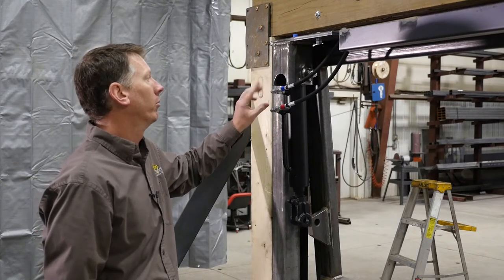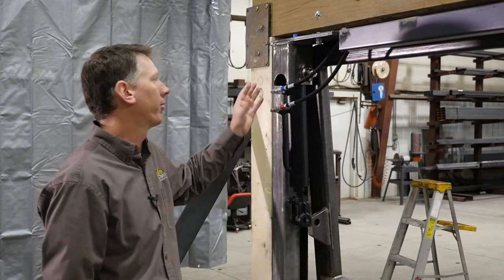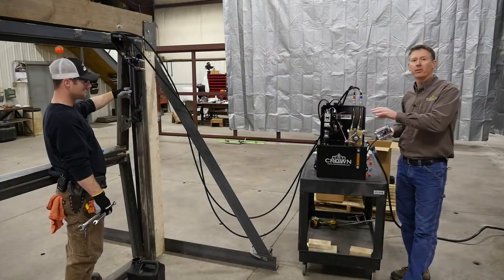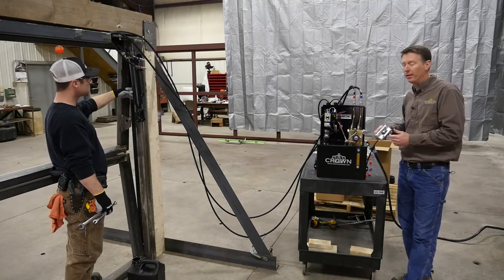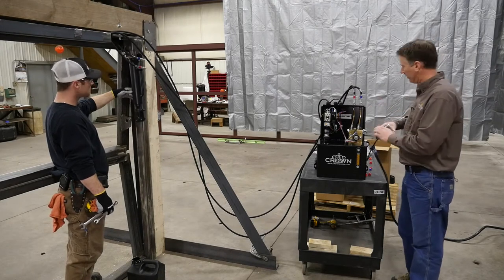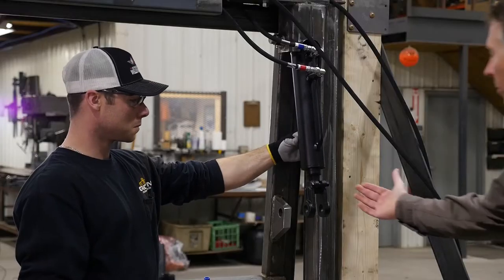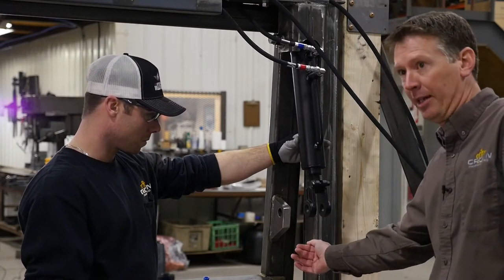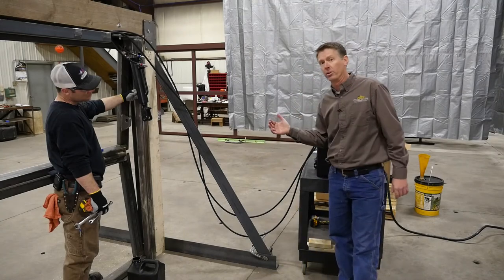All of the hydraulic connections we have do not need any kind of thread tape or sealer — they are a flared fitting, just tighten them and you shouldn't have any leaks. Blue lines are purged, hooked up to the cylinder, and fittings are tight. We are now going to run it in open mode and extend the cylinders. When you're doing this, make sure you're holding out the bottom because it's coming down with some force. Make sure that area is clear, and run it until both cylinders are fully extended.